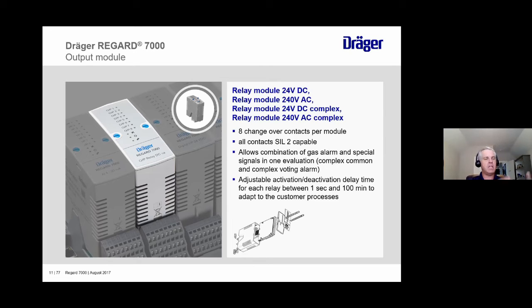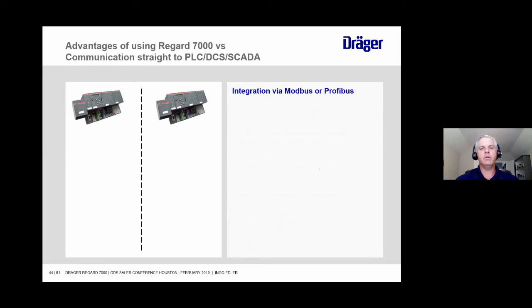So let's say for the same example, you wanted all 4 of those points to go into alarm for a certain amount of time before you actually trip that big mitigation step. Well, you can configure that with a Regard 7000 versus having to program that feature into a DCS system or a safety PLC. That's some of the differences. So next I want to talk about the differences between us talking to a Regard 7000 system versus going straight back to a PLC or DCS.